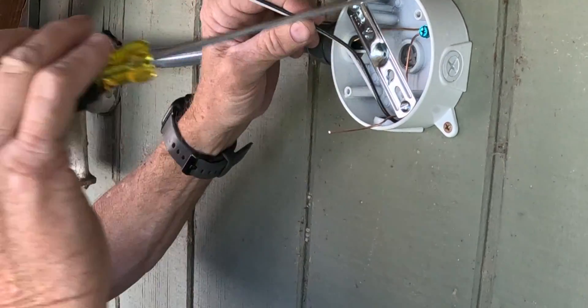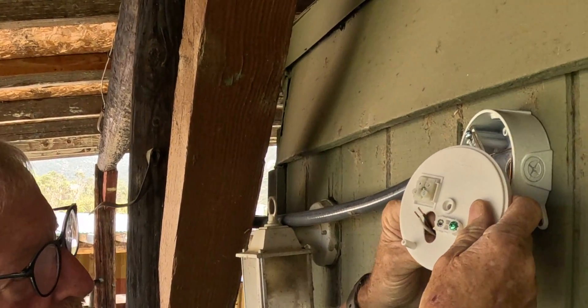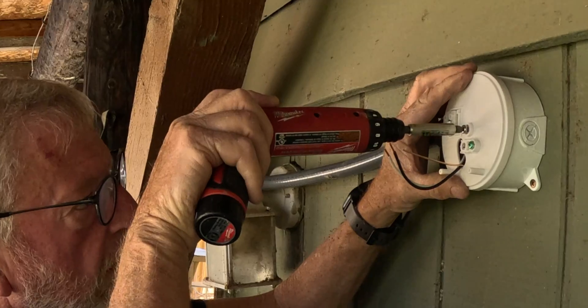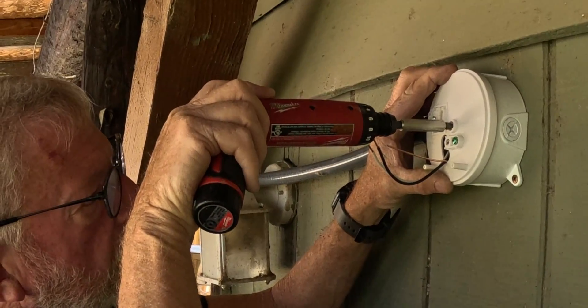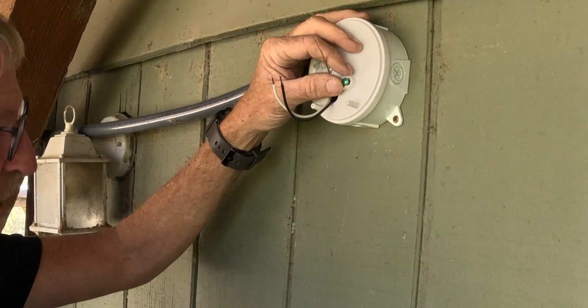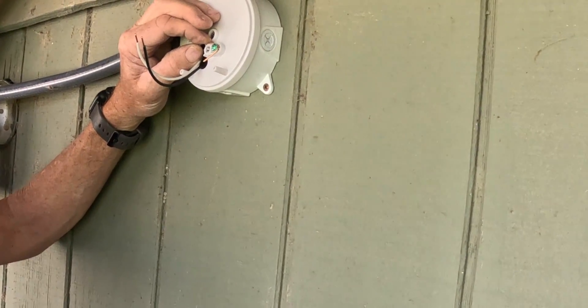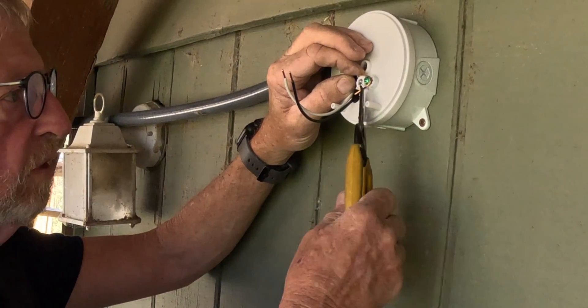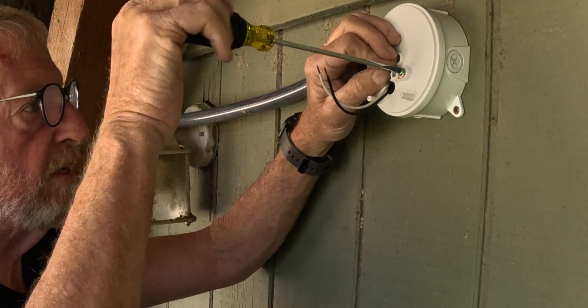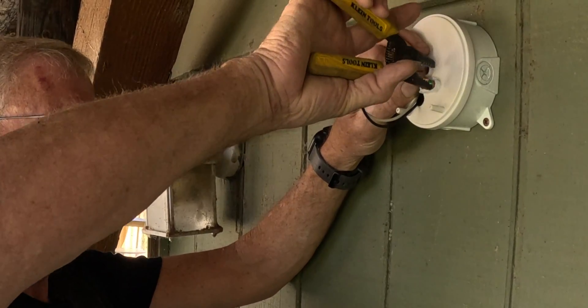As we know from the other one, we just need a little bit of wire right to about there. The arrows right there, straight up. Now the ground wire to ground the base of the fixture. Do you have to use both? One ground wire is for the box and the other ground wire is for the fixture itself. So yes, you do use both. Every time you ground something, make sure your box is always grounded and then your equipment is grounded.